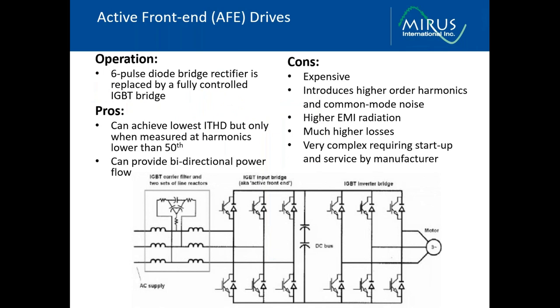In active front-end or AFE drives, the input rectifier is replaced by a fully controlled IGBT bridge. So we can see the IGBTs shown here. So essentially, the active front-end drive has two inverter sections. So it is basically twice the size of a conventional six-pulse drive. It is true that these AFE drives can reduce harmonics in the low end. So if we're measuring up to the 50th harmonic, we will see a substantial reduction in the input current into the drive. But we need to consider the fact that these devices also introduce higher frequency harmonics.